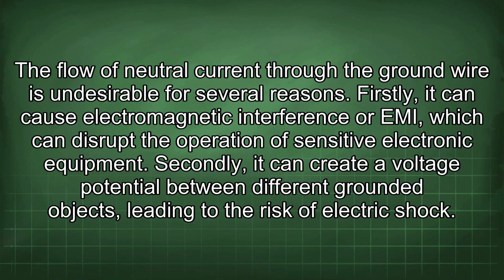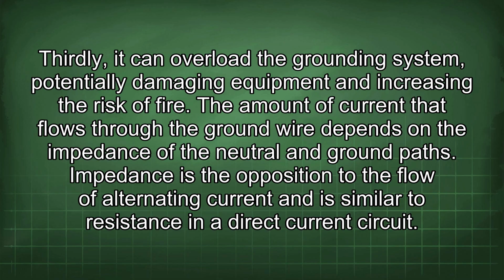The flow of neutral current through the ground wire is undesirable for several reasons. Firstly, it can cause electromagnetic interference, or EMI, which can disrupt the operation of sensitive electronic equipment. Secondly, it can create a voltage potential between different grounded objects, leading to the risk of electric shock. Thirdly, it can overload the grounding system, potentially damaging equipment and increasing the risk of fire.